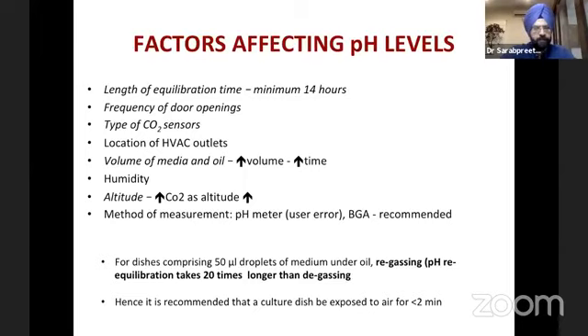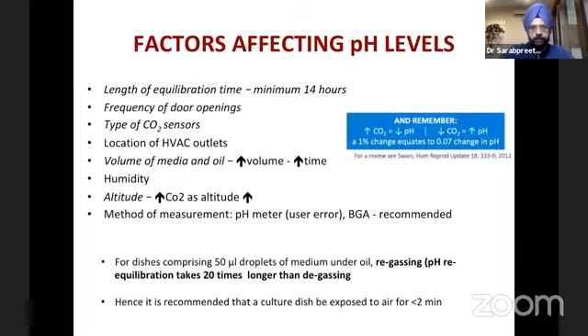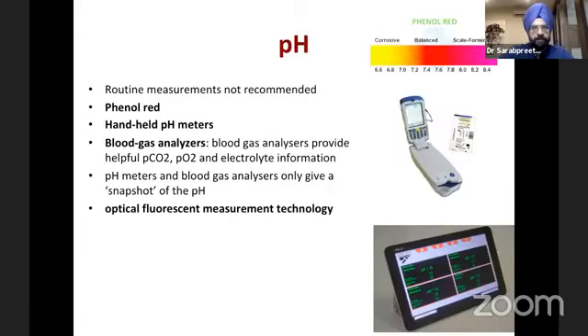Just to emphasize the importance of keeping the dishes in a constant environment, if you bring out a dish containing 50 microliters of medium under oil, regassing takes around 20 times longer than degassing. Therefore, it is recommended not to expose the dishes for more than 2 minutes. Always remember that an increase in CO2 by 1% is equal to a 0.07, or roughly 0.1, change in pH. This is just the devices which are used to measure pH, and nowadays there is a real-time device available, which is shown in green color in the right bottom. So you can use this, but then it doesn't rely on a standard that might affect the pH of the media.